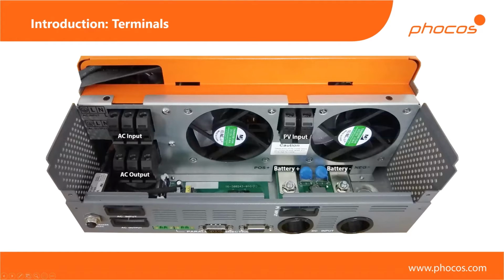The terminals that are required here, the cable shoes that you crimp around, because we need big cables here. We're dealing with 100 to 200 amps of current on the battery side to be able to handle those 5 kilowatts or even 10 kilowatts for 5 seconds. So we basically include those terminals inside the packaging from the inverter.